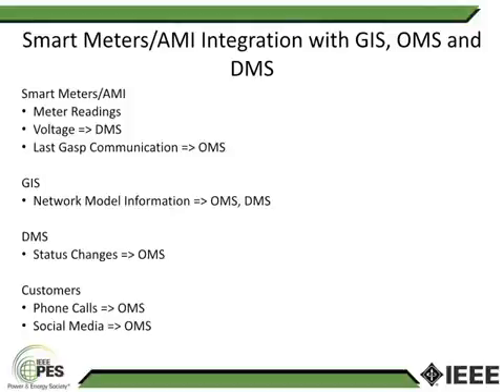The Geographic Information System, the GIS, is the reference system for the network model for both the OMS and DMS. We also want the DMS to know whenever a circuit breaker or feeder breaker changes state, like going from closed to open, within a couple of seconds. That information needs to get to the outage management system because the OMS knows which customers are connected to that feeder, so if it was de-energized at a certain time, OMS knows exactly which customers are affected.